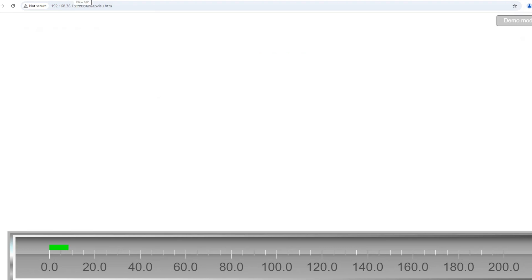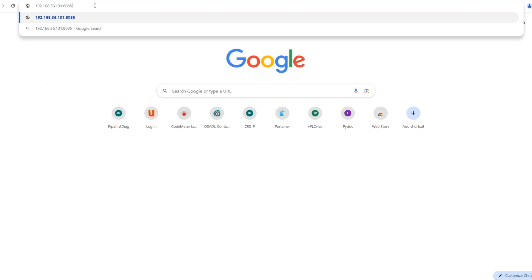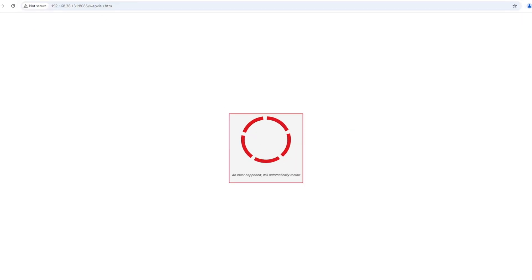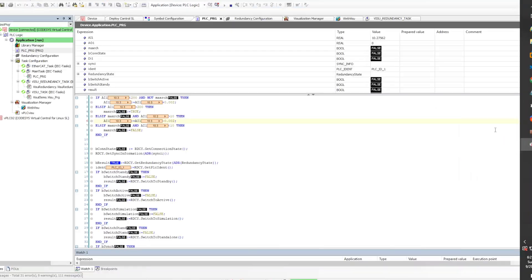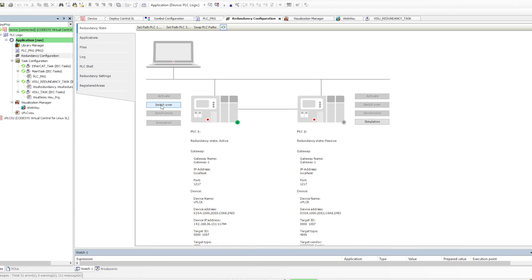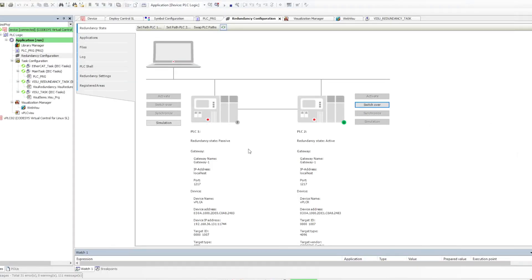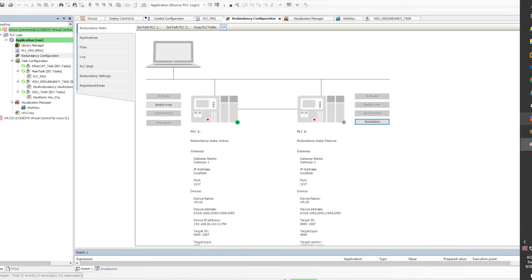To demonstrate the switchover visually: I have port 8084 open showing the visualization, and I also open port 8085. Port 8085 is still in connecting phase. When I go to the redundancy screen and click 'Switch Over', the active becomes passive and the passive becomes active. Going back to the visualization, 8084 goes into connecting and 8085 connects and shows data — that's exactly how the switchover works.